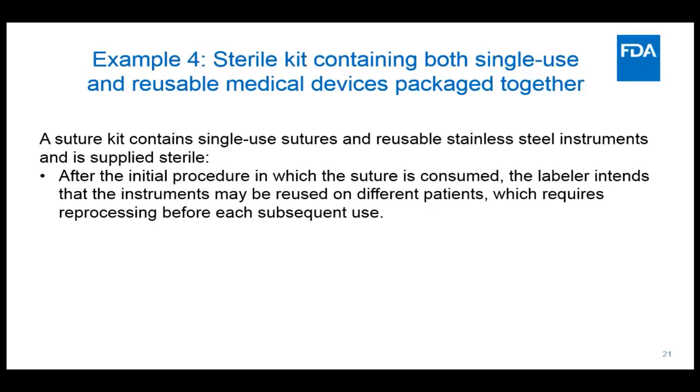Correct, like the direct part mark that goes on these two individual products. There is no way to link the individual devices to the package. When there's an assorted package, there's not an easy way to do that. You're not required to put on the label of the two separate devices the UDI of the package they may also come in. But when stakeholders are looking at your data in GUDID, it's useful, like in the device description, to make that relationship clear to people.